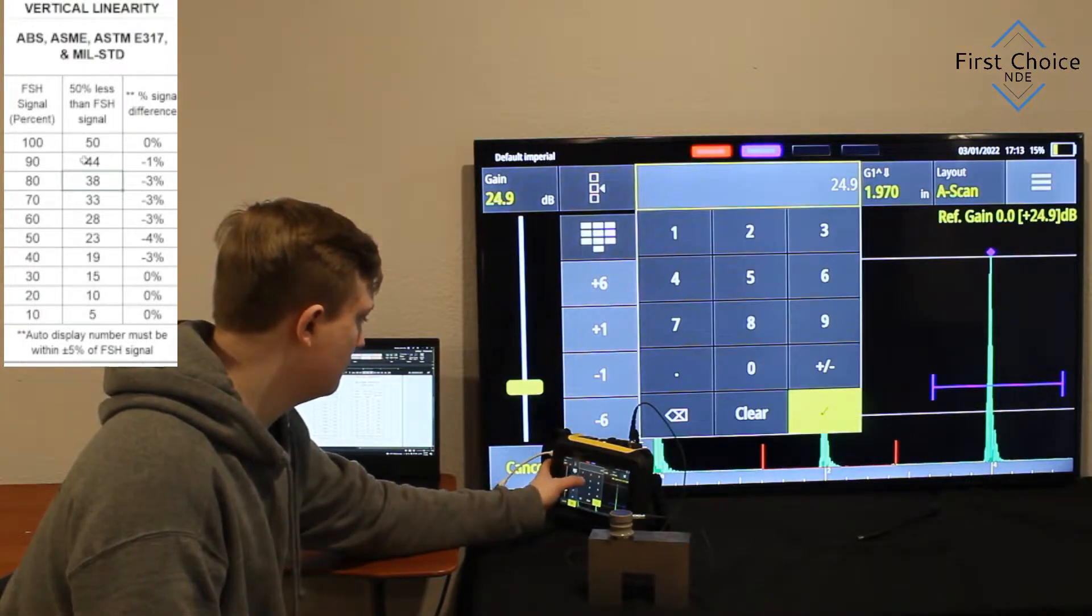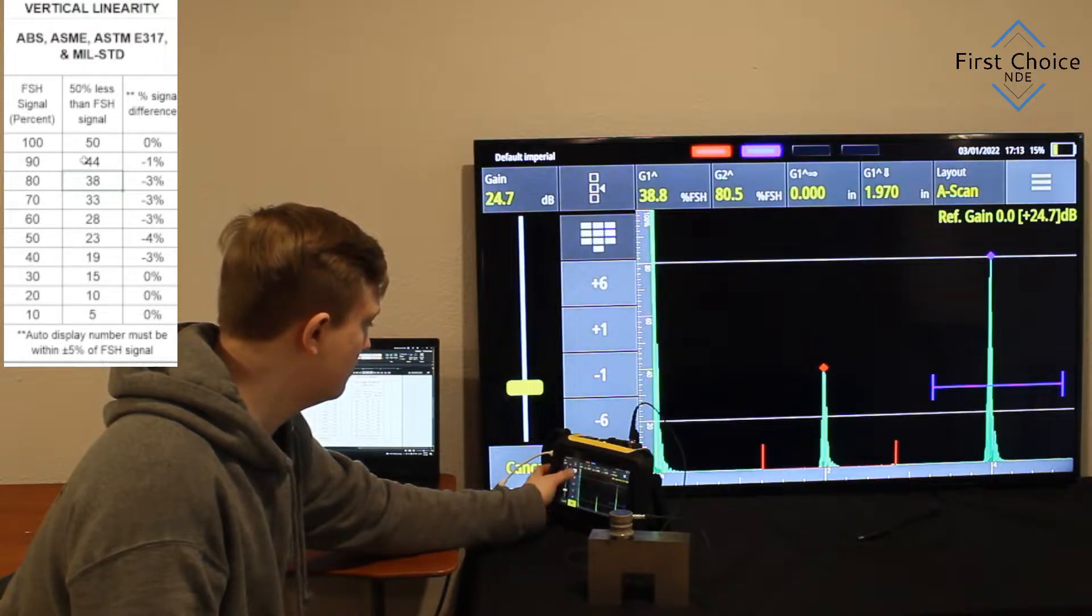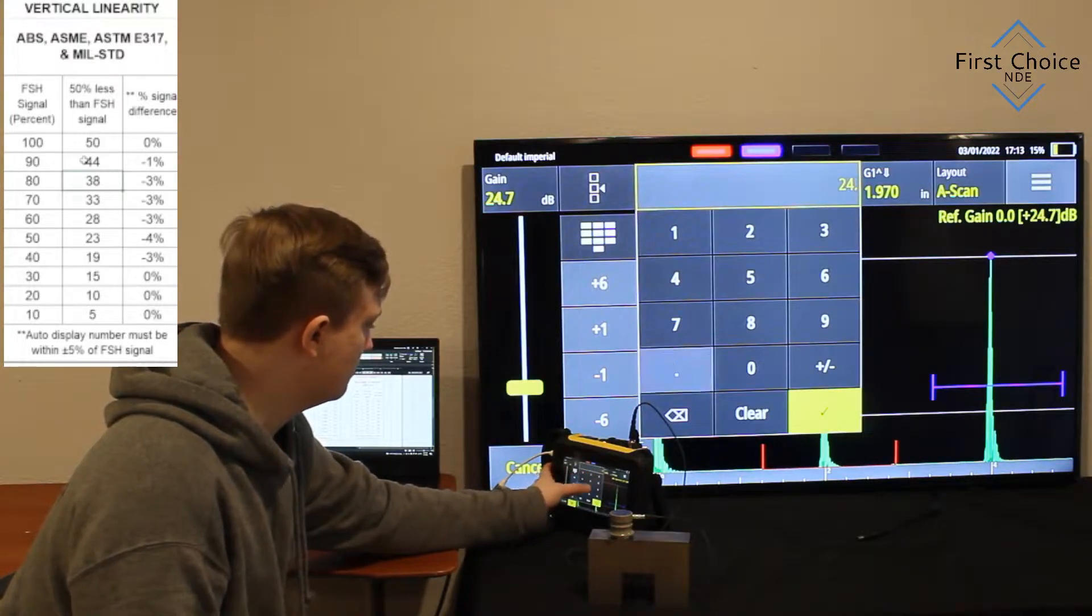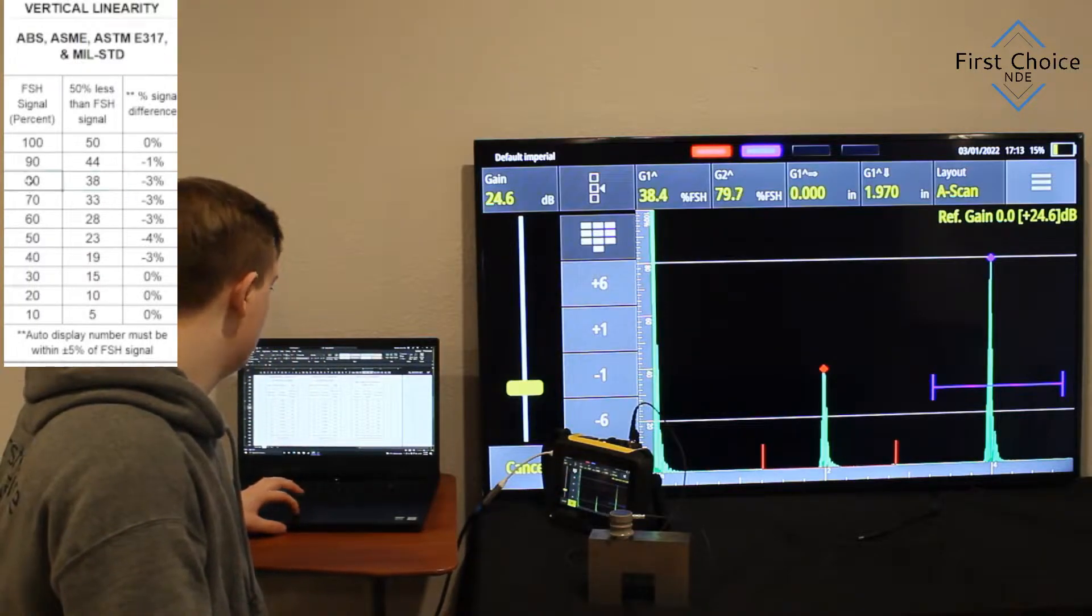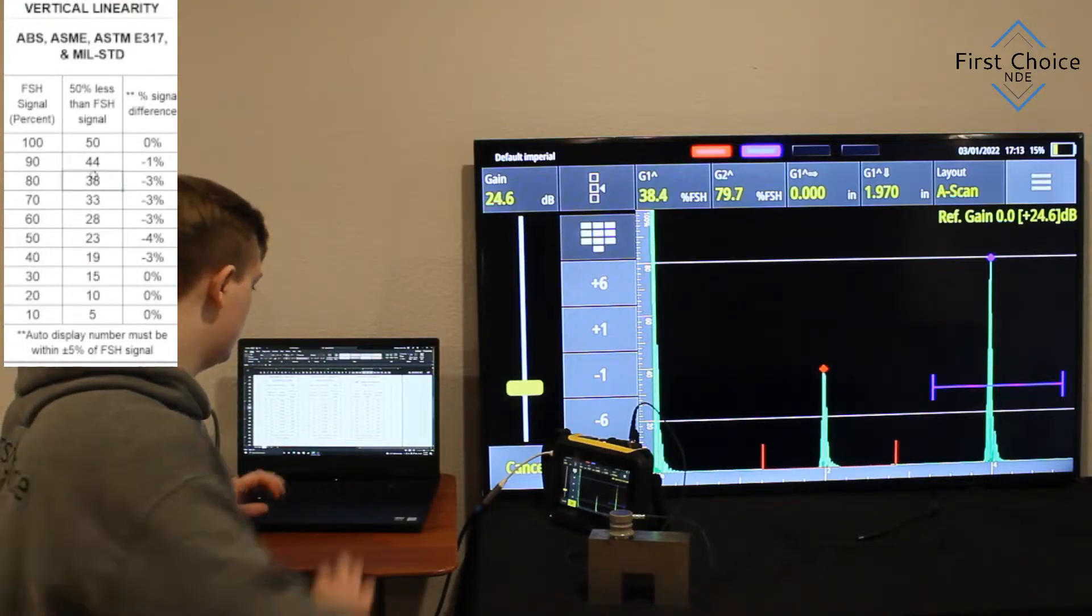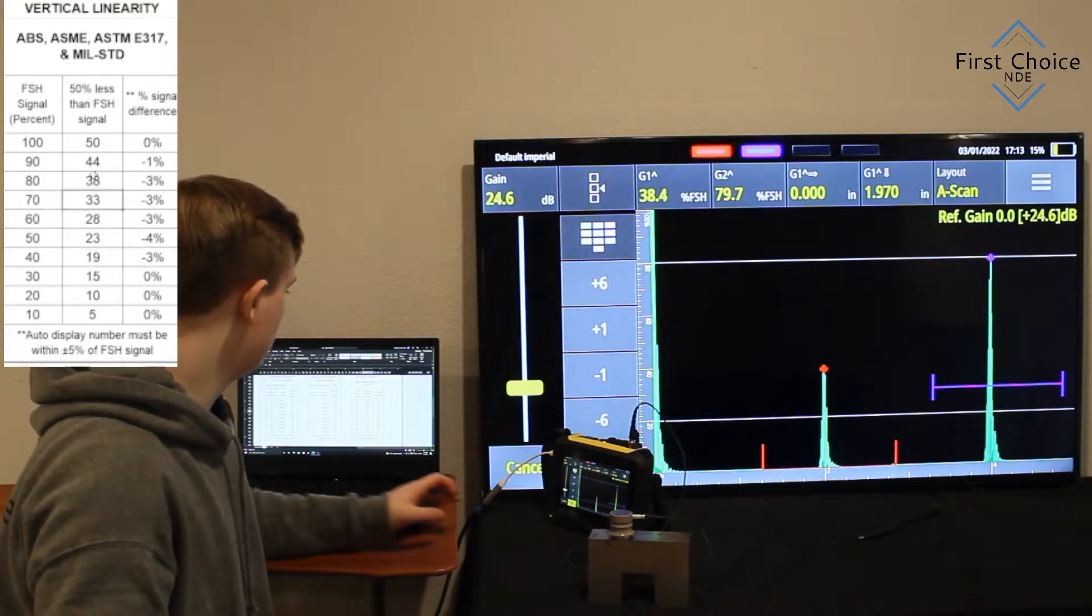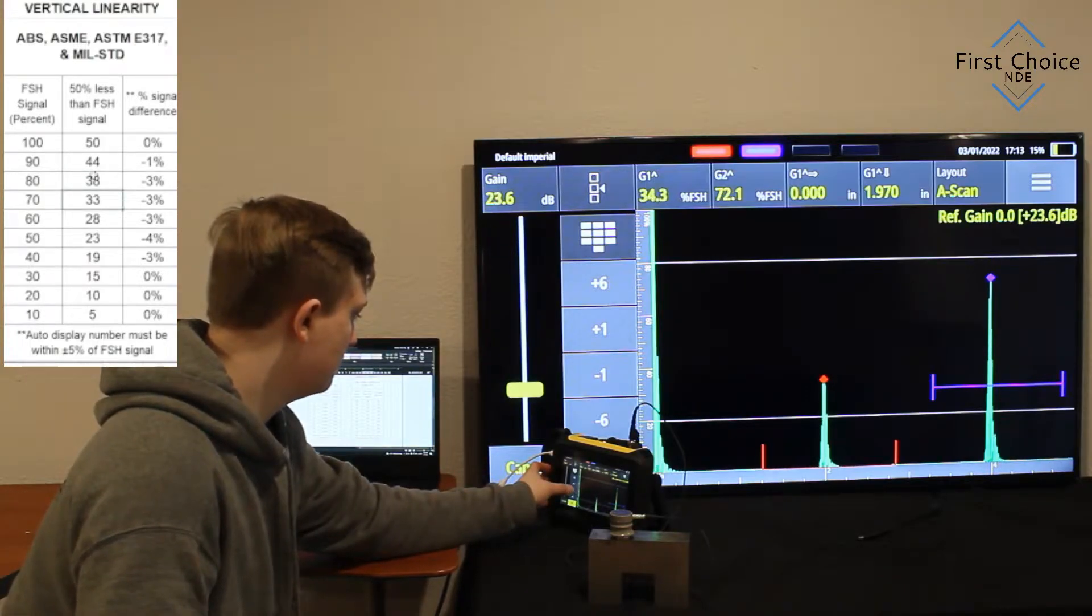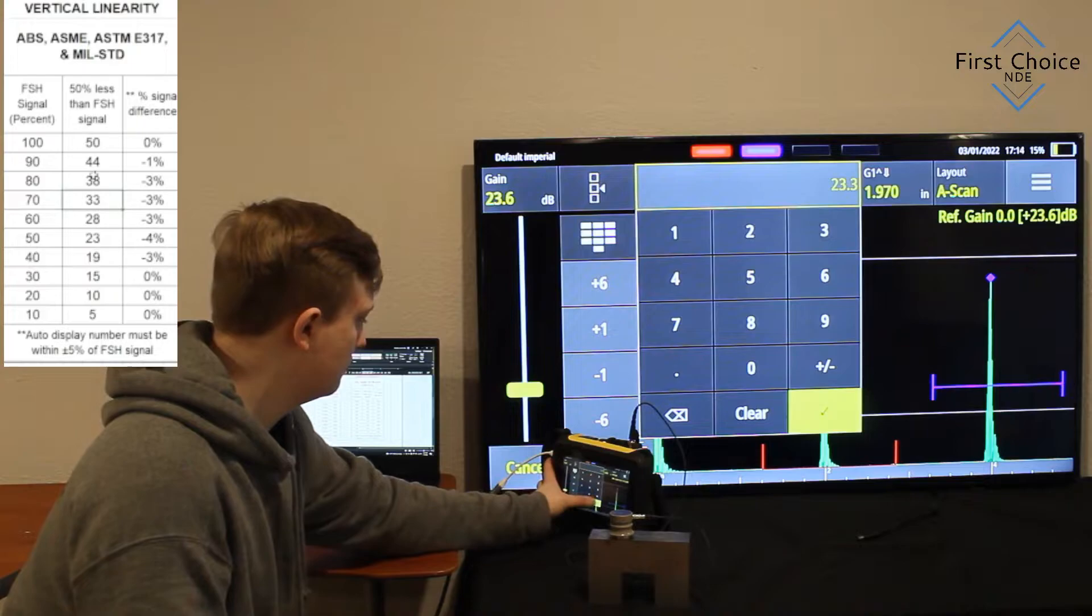Alright, so we'll just go again, lower the dB, make sure that the signal on the right is at 80%. And we're just about there. And we're going to end up with 38% screen height on the left signal. And you see our percent signal difference, you're allowed to have plus or minus 5% of the initial signal. So as you see, on our 80 to 38, we had a minus 3% signal differential, which is okay.